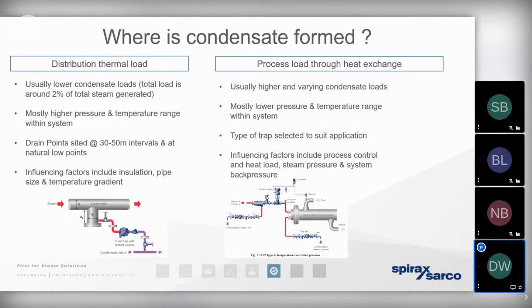And we remember, there's far, far less energy in the condensate than there is in steam. Unless we're getting rid of that condensate, we're more susceptible to that erosion, corrosion, and water hammer.